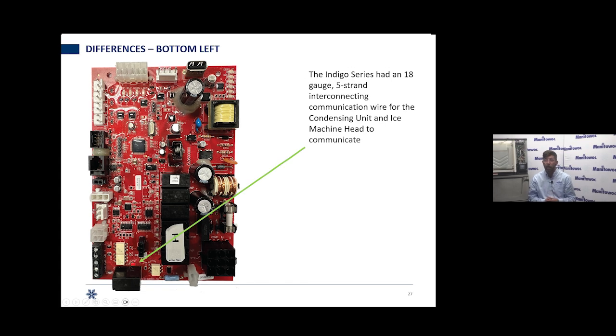All right, but also there's a difference here at the bottom left that you'll see, that CVD relay. The Indigo series ice machine had a 5-strand 18-gauge wire that allowed the outside unit, the condensing unit, to communicate with the inside unit, as we refer to the ice machine head. It allowed us to see what the low pressure and high pressure switches were doing outside, and it would allow us to communicate, get the machine to shut down, and ensure that the full bin delay and everything else was going on. This is not present on Indigo NXT. There is not communication between the two units, and that light would be there.